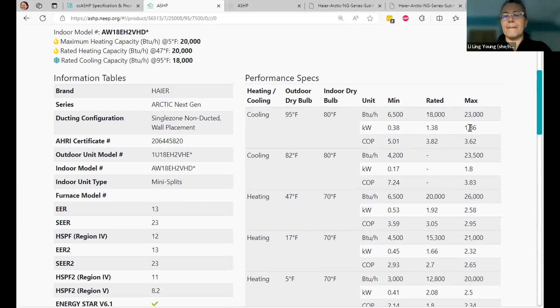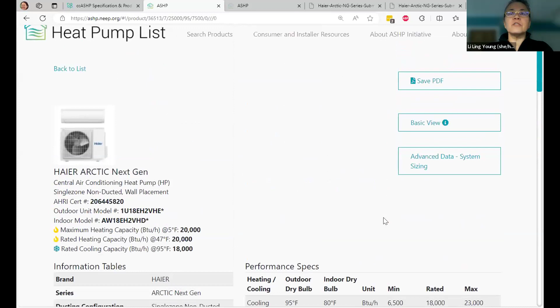Okay, so on the right here, these performance specifications show you at different temperatures what the capacity is and the efficiency. Look right down here, cold weather performance, 5 degrees. It's showing you the minimum capacity, the maximum capacity, and the coefficient of performance, which is the efficiency at this temperature. This is not a seasonal efficiency, it's just at 5 degrees what's the efficiency. That's really useful information.